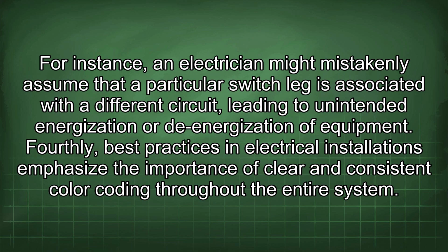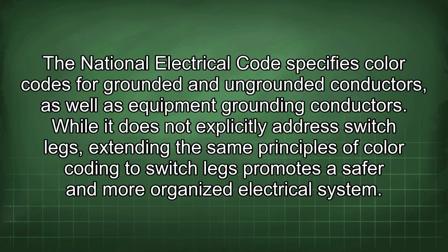Fourthly, best practices in electrical installations emphasize the importance of clear and consistent color coding throughout the entire system. The National Electrical Code specifies color codes for grounded and ungrounded conductors, as well as equipment grounding conductors. While it does not explicitly address switch legs, extending the same principles of color coding to switch legs promotes a safer and more organized electrical system.